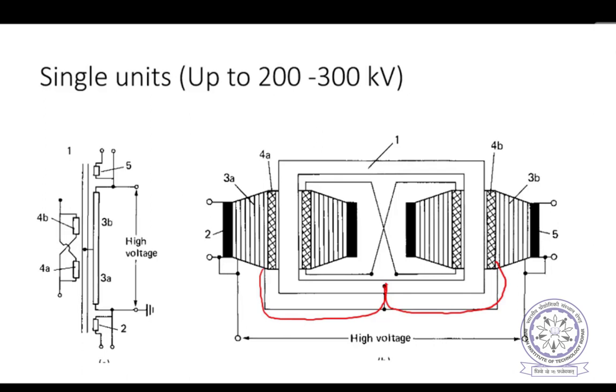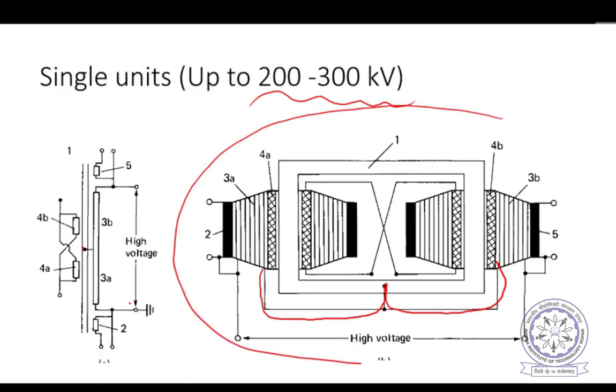So without changing the insulation level, we can achieve voltages up to 300 kilovolts, because the maximum voltage difference between the core and any lead will be around 100 kilovolts only. So for the same insulation level, we can achieve almost double the voltage. This is another type of construction for generating high voltages using just single units.